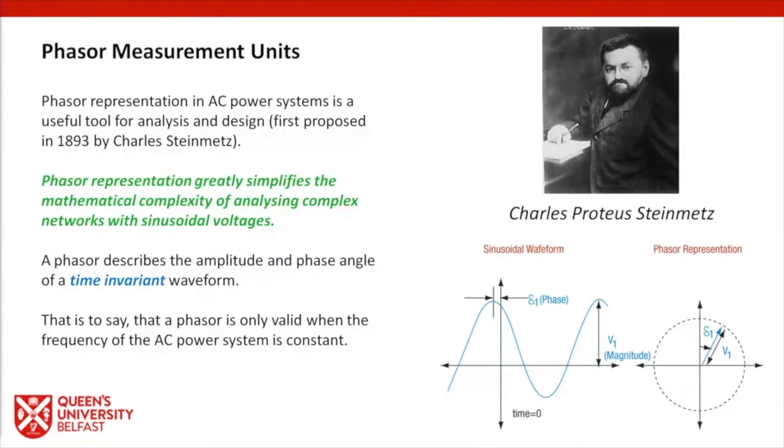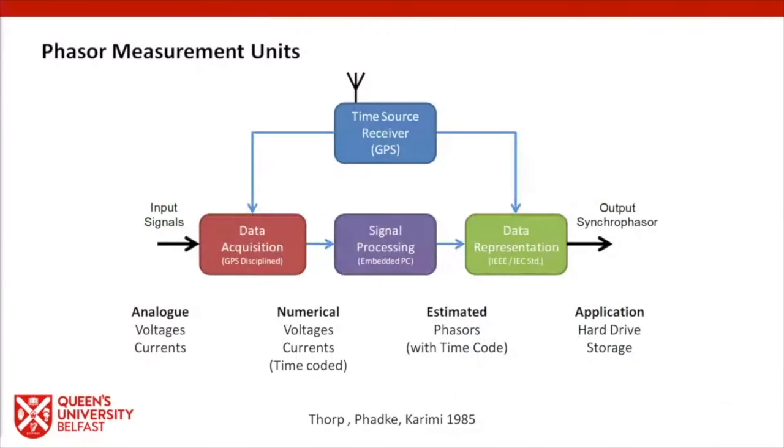That's an issue at transmission networks, but again, it's something that actually we have a little bit of a benefit in terms of the distribution network. Because sections of distribution network are so small, we don't tend to see phase oscillations across them. It would be very unusual to end up in such a situation.